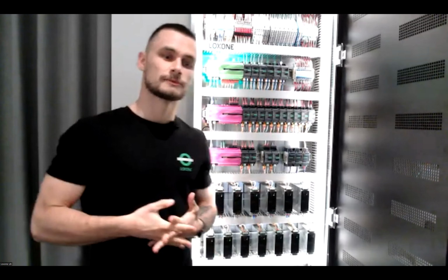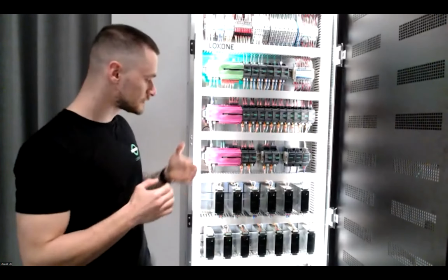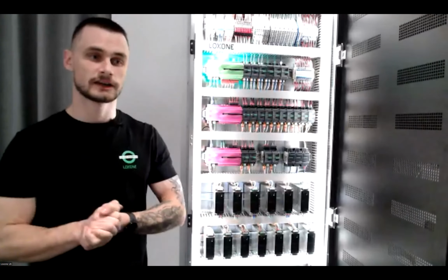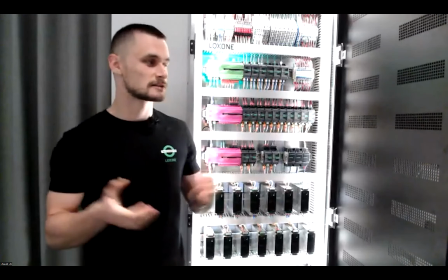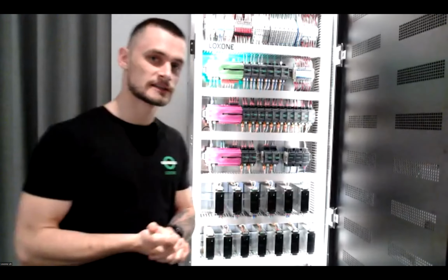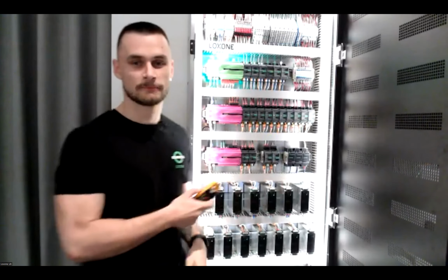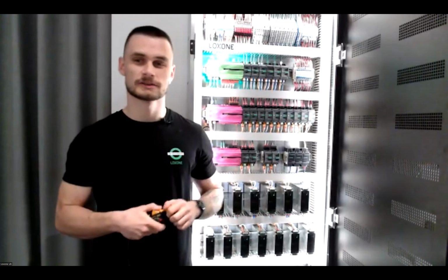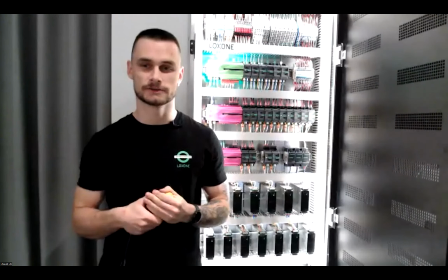What we found out is whenever we spec out to that high of an extent, we tend to have a lot of power supplies that are never getting in use. And it is something that we can quite easily test and check. If you just have a clamp meter, you can clamp it on every single circuit, you can max it out, you can see how much power we're actually using.